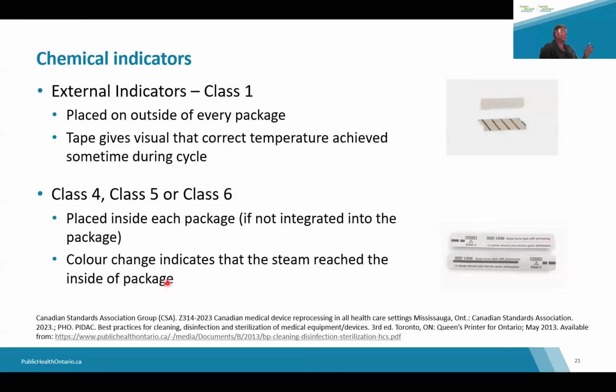So you place this inside each package if it's not integrated into the package. And when you are taking the package out, if you have a pouch, you look to see either inside the package or if it's integrated, that the chemical indicator has changed to the color that it's supposed to change to. If it hasn't changed, then you have a concern and you need to figure out what went wrong with that particular cycle. Oh, I see I'm getting a funny stripe across my head.